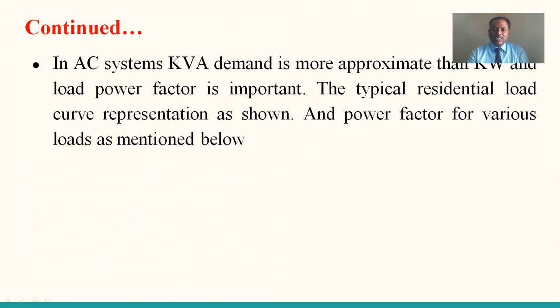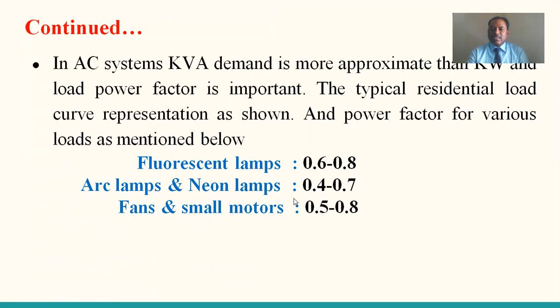But nowadays everything goes to fluorescent tubes. They have hardly 0.6 to 0.8 power factor. Similarly, arc lamps and neon lamps we are observing have very low power factor, from 0.4 to 0.7. And for fans and small motors, fans consisting of single phase induction motors, it is hardly 0.5 to 0.8. And electronic gadgets, 0.6 to 0.8 power factor.